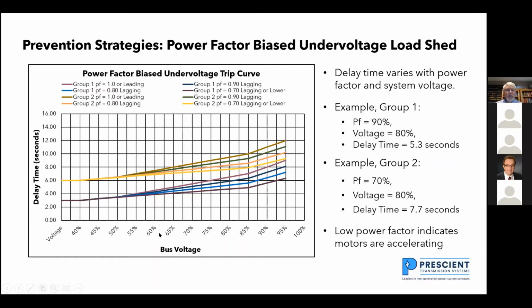And what we've done is we developed some relay characteristics to show that. The under voltage devices I use today are simple change of state items. If voltage drops below 90% and for 2 seconds or something like that, the relay would operate. And we're thinking that you need power factor biased under voltage trip curves. If I have a really poor power factor, that's what I'm showing here.